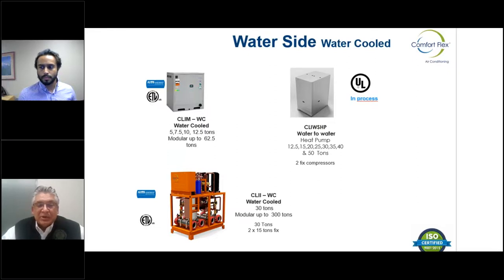So if you think about this, we talked earlier about an application where you have, let's say, a 100 ton machine or 200 ton machine, and you needed 20 or 30 tons during the shoulder season, and the current machine that's installed really can't run that low because of limitations in its capacity control or the design of the chiller. You can actually add one of these as a side stream chiller for low load capabilities during the shoulder seasons, and also provide hot water for heat recovery for places like hospitals, hotels, anything that needs hot water year round, for laundry, kitchen, those kinds of things. It works out really well for that application.